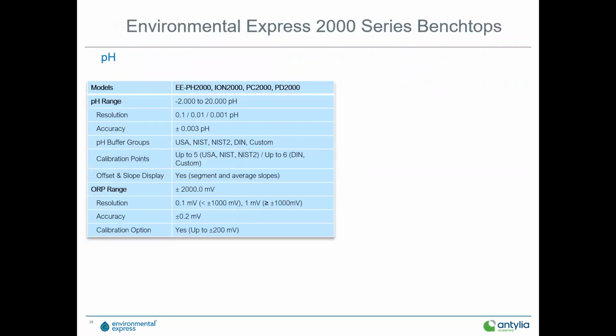All right, so take a look at the range on the 2000 series. It's a -2 to 20. As I mentioned, 0.001 resolution max. The accuracy on this instrument is killer, 0.003 plus or minus pH. Now, in addition to the accuracy of the instrument and sensor, you have to add on the accuracy of your buffer. So that's where buffer is a key part of the overall system accuracy. You literally add those two values together, that gives you the system accuracy.